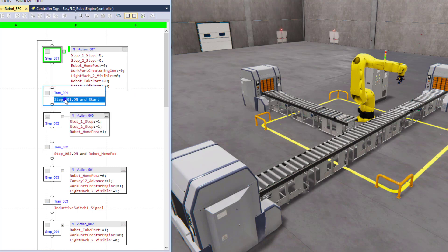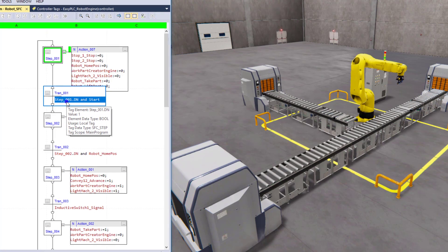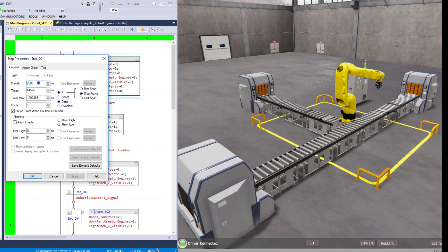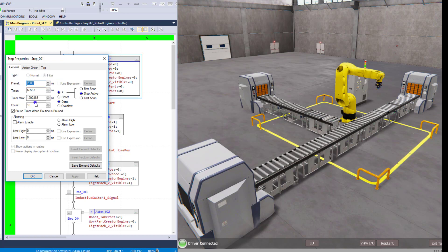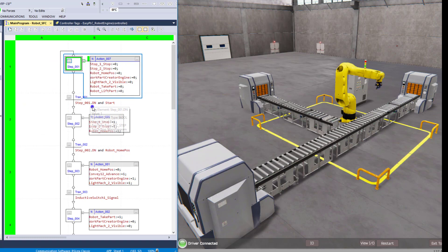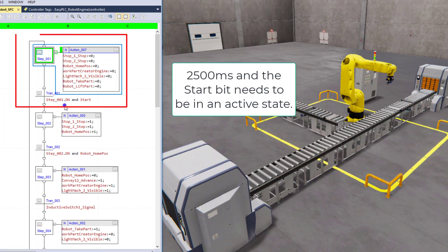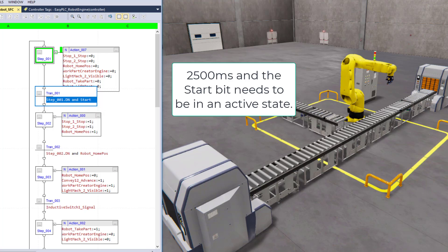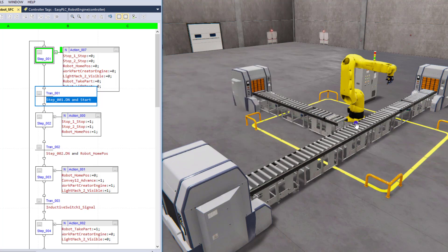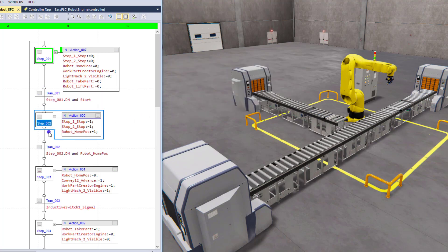The transition to get out of that step is waiting on Step_001.DN, which is the done bit. We have a timer on that done bit — it has to be in this step for at least 2,500 milliseconds, which is basically two and a half seconds. So no matter what, we need to be in Step_001 for at least two and a half seconds. The start bit also needs to be on — and as you can see, the start bit is not on at this current time. As soon as we turn that start bit on, it will transition to step two.